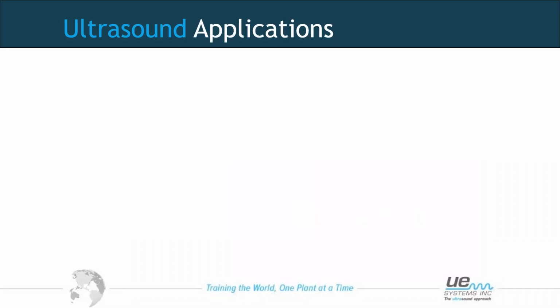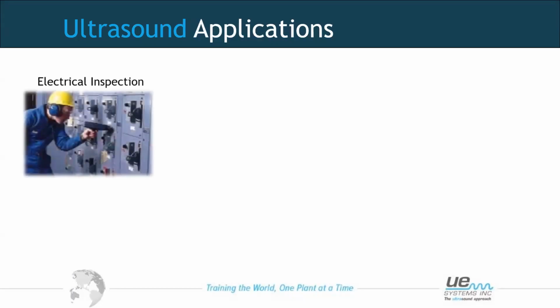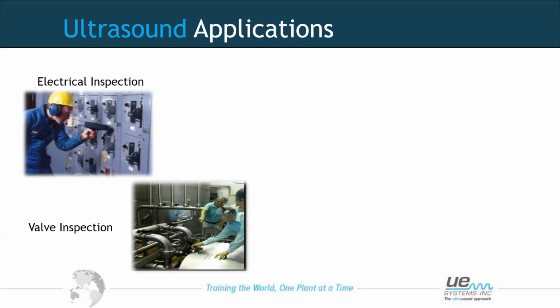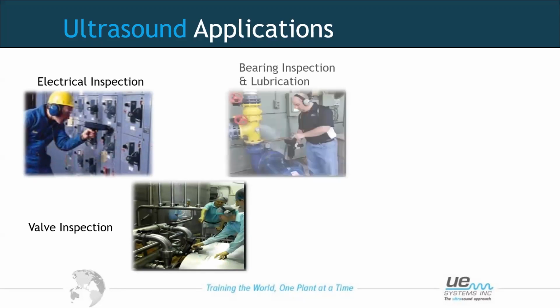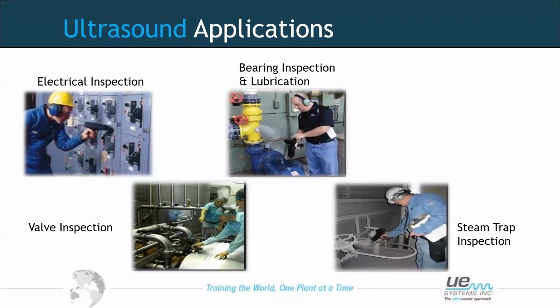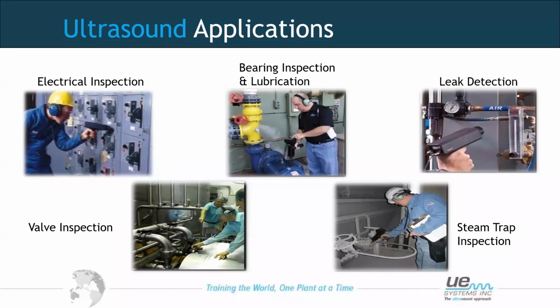So let's have a little look at the applications where we can use ultrasound. I'll cover these now briefly and then we'll go into more detail with them afterwards. The first one being electrical inspection. Using ultrasound to detect valve leakage for valve inspection. We can also use it for bearing inspection and ultrasonic lubrication. We can use it for steam trap inspections as well to understand the condition of the steam trap. And also, one of the bigger uses, using it for leak detection.